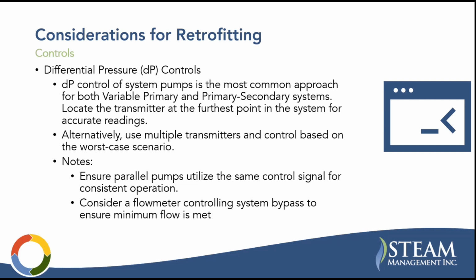Considerations for retrofitting. So controls, differential pressure controls. We're talking about DP control of the system pumps. This is the most common approach for both variable primary and primary secondary systems, where you're going to control the pumps based on a DP set point. You're going to locate that transmitter at the furthest point in the system so that you're making sure that there's appropriate DP at all users. Your furthest points can be your most constraining point, right? Alternatively, you can use multiple transmitters and then control to the lowest signal. And you want to ensure that if your pumps are operating in parallel, that they're using the same signal for consistent operation. And you're going to want to consider a flow meter to control the system bypass to ensure that the minimum flow is met.